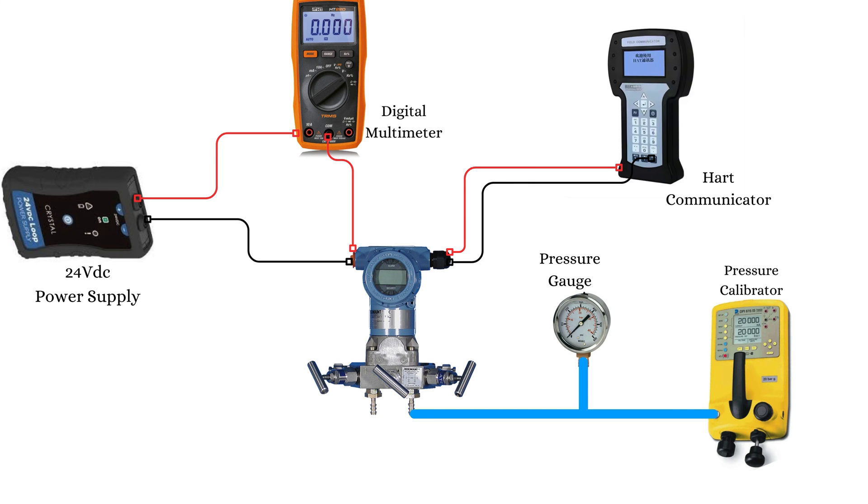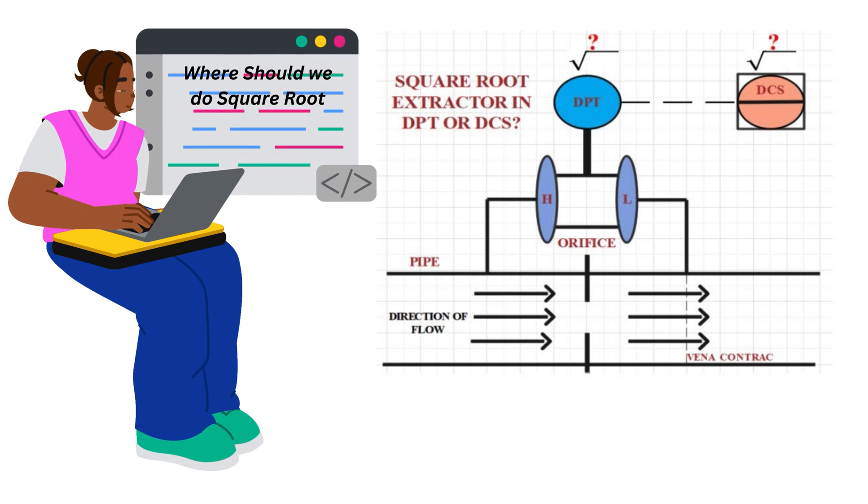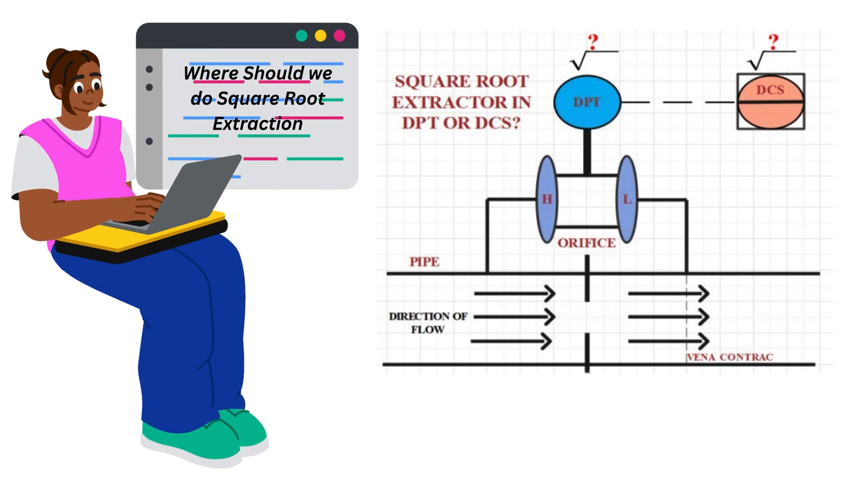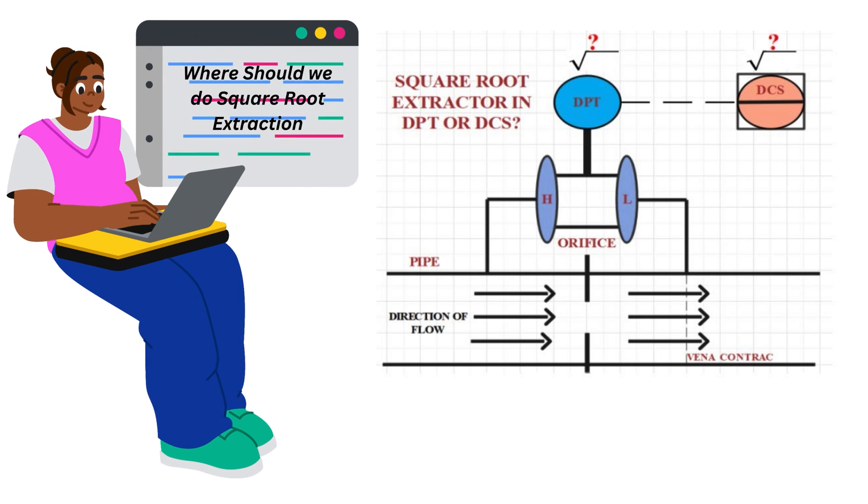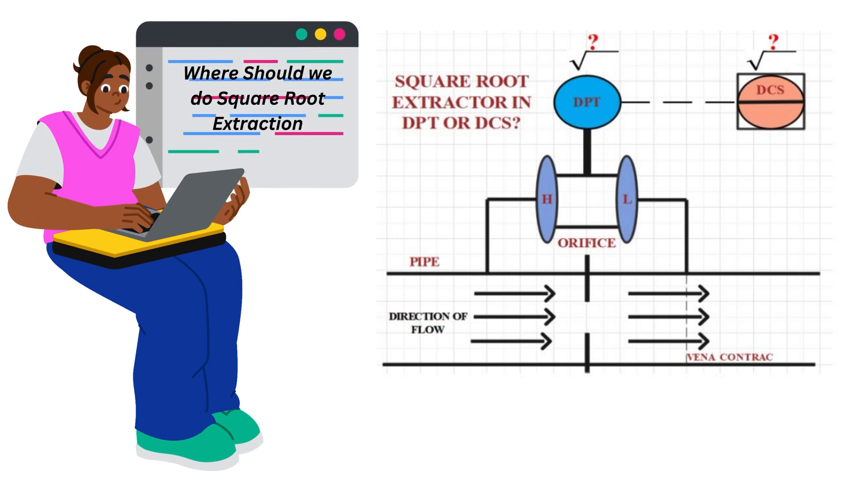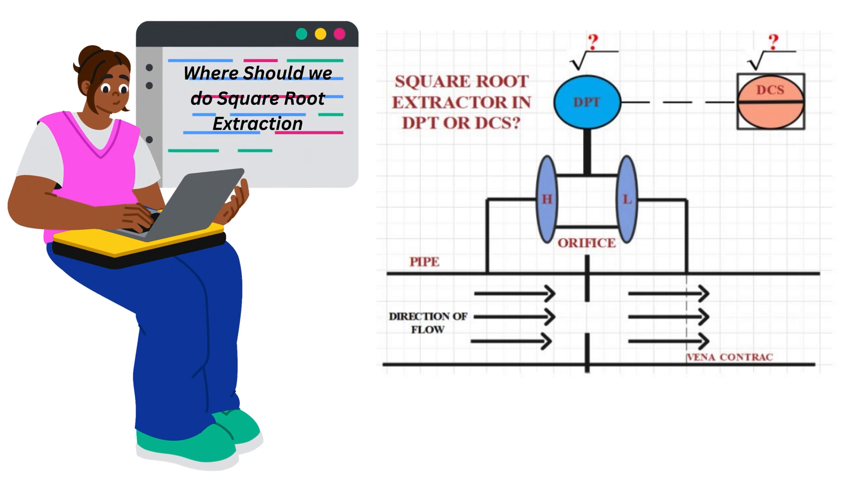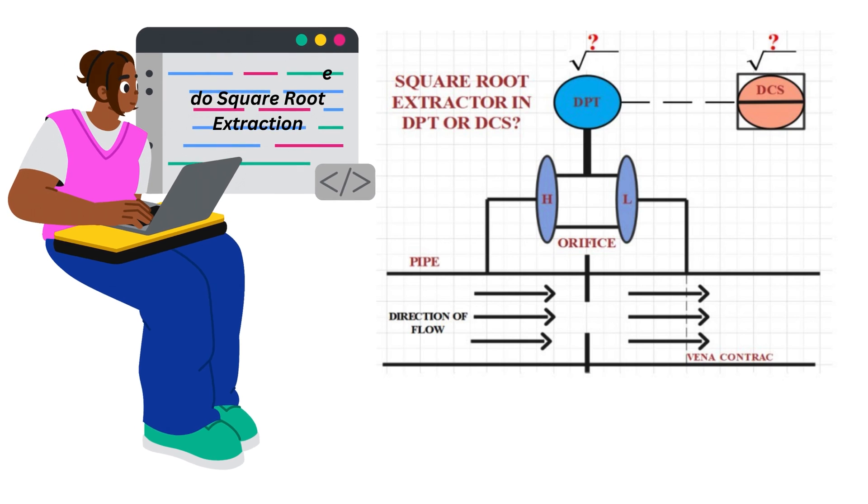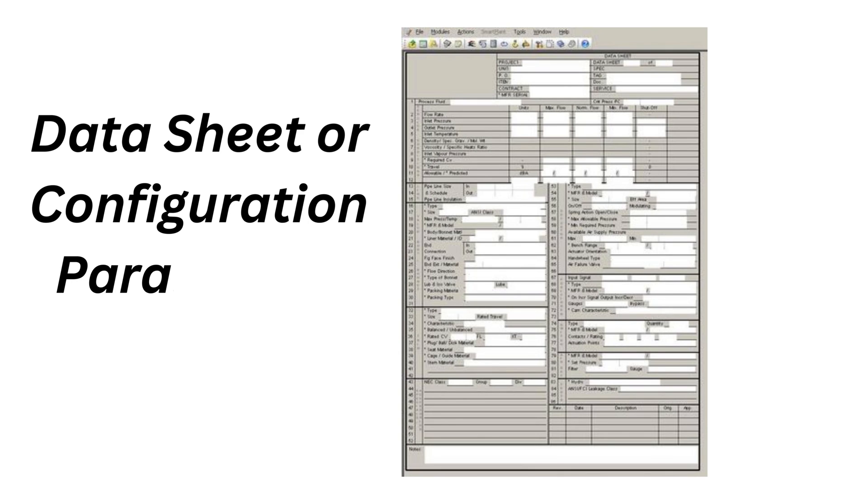Prior to starting the calibration, it is necessary to determine whether the square root extraction takes place in the DP transmitter or in the PLC-DCS. The output value in mA of the DP transmitter will depend on where this square root extraction occurs. So check the datasheet or the configuration parameters of the DP transmitter to see if the transmitter does the square root extraction.